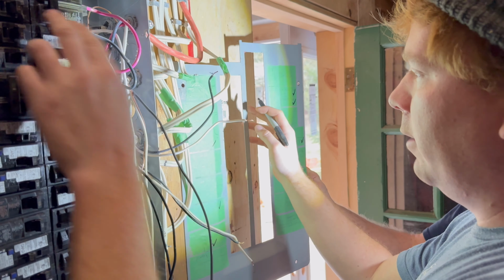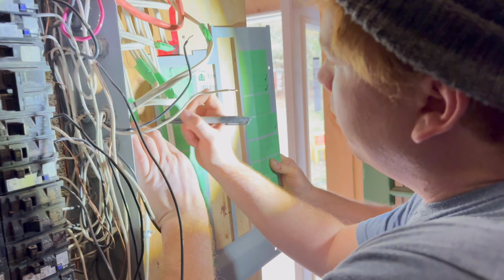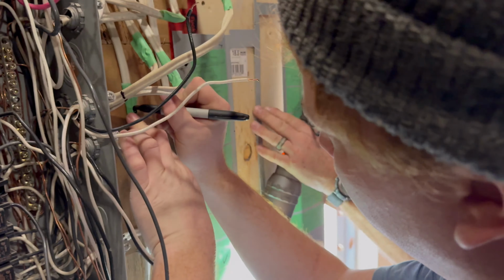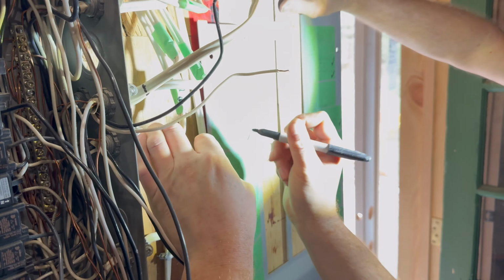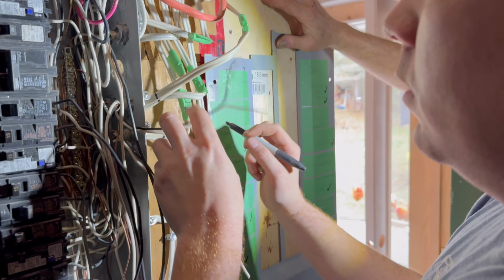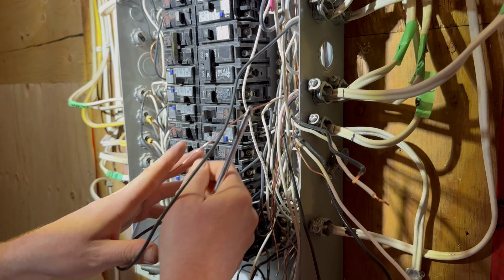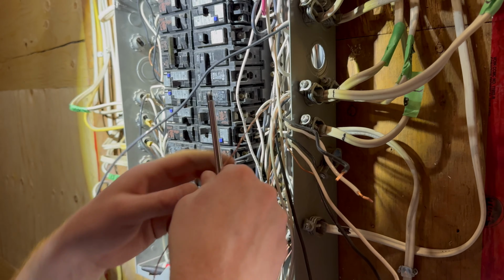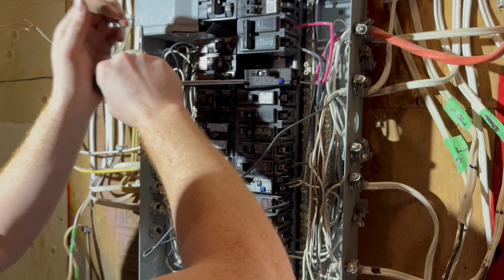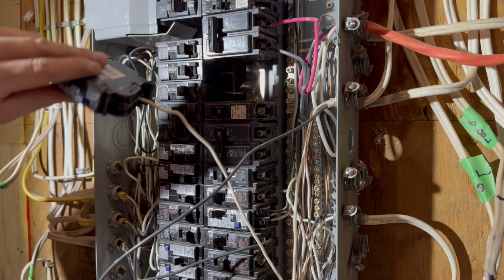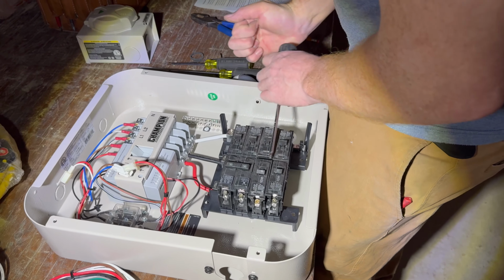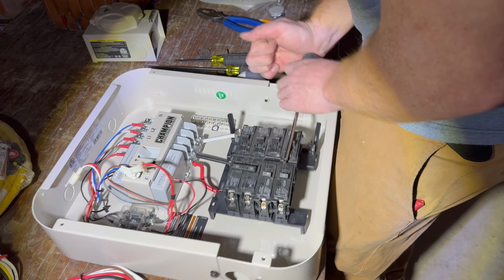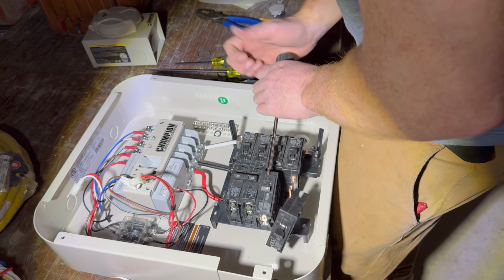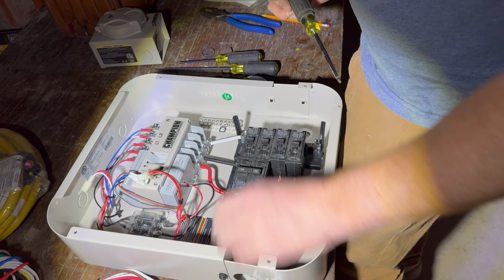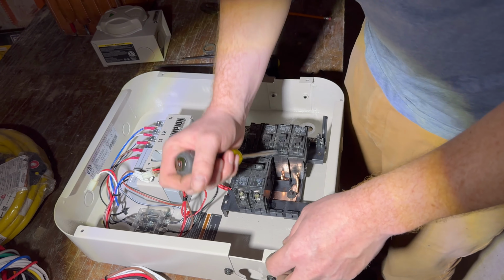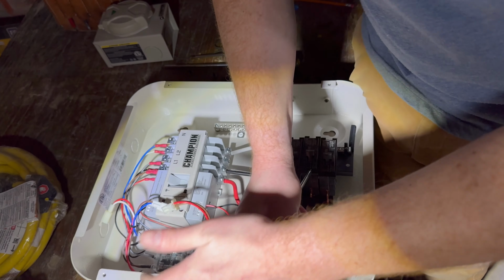There's usually a lot of wire and cable involved in an installation like this, so it's important that you label everything carefully so you get the correct circuits directed for generator powering. Here Mark is removing the arc fault protected circuits from the existing panel and moving them to the manual transfer switch panel. Because the transferred circuits are arc fault protected per local code, Mark is required to replace the manual transfer switch breakers with AFCI breakers. Always be sure that any breaker you install is rated for the panel it's going into.